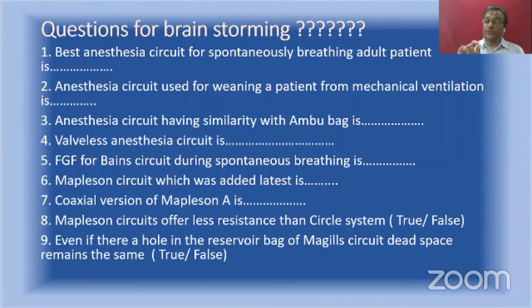Even if there is a hole in the reservoir bag of a Magill circuit, dead space remains the same. See, consider a hole in the reservoir bag. Now, the APL valve has become non-functional because whenever the pressure in the circuit increases, the expired gas, instead of going through the APL valve, will be going through the hole in the reservoir bag. See how much increase has happened to the dead space. The dead space has extended from the patient towards the reservoir bag, including the breathing tube. So, a dangerous increase in the dead space has happened. So this statement is false.